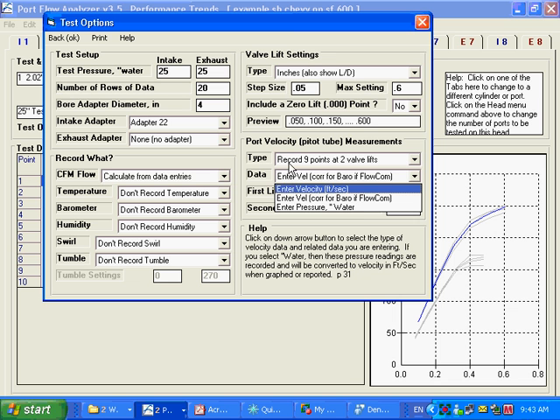If you got a barometer reading, you can actually correct for it, since barometric pressure changes the feet-per-second conversion from inches of water. This gives you that choice. You can do it with our black box too, but you have to ask to get a barometer sensor installed. There really isn't much advantage to it, though, because you're not so much looking for the absolute flow velocity as the difference in flow velocity across the cross section of the port—like whether it's high velocity in the upper left corner and low velocity in the lower right corner. Whether you correct for barometer or not, you'll see the same trends, so there isn't that much advantage in doing it.